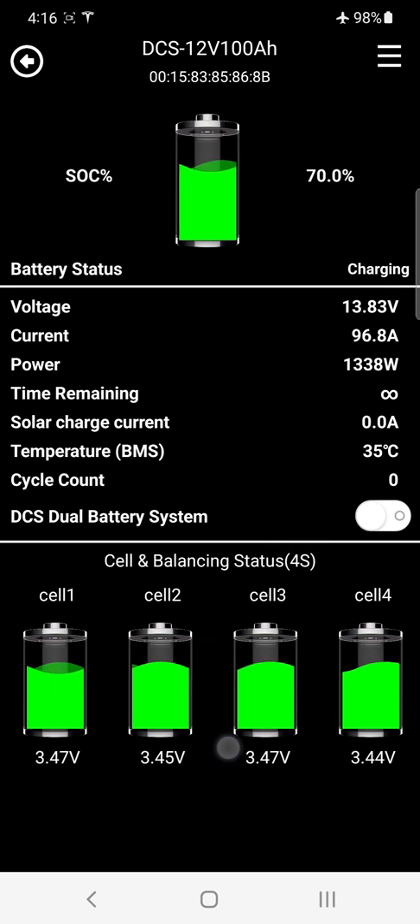Cell and balancing status: a 12 volt battery has four series cell connections. This is a brand new pack straight off the shelf, and at 100 amps you can see the four cell voltages — 3.47, 3.45, 3.47, 3.44 volts — very close. Because we run an active cell management system, you can see the cells actively balancing every time you charge, dynamically matching up the cells for maximum service life.